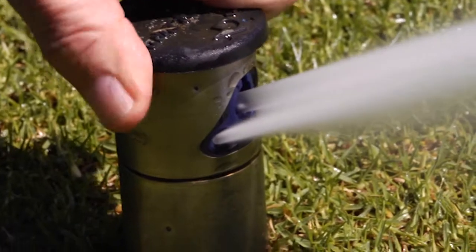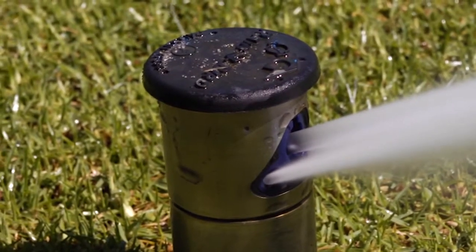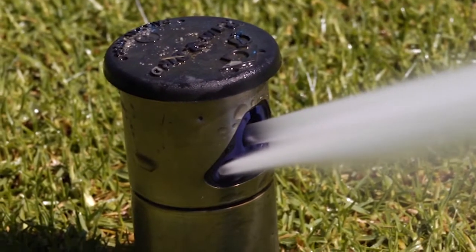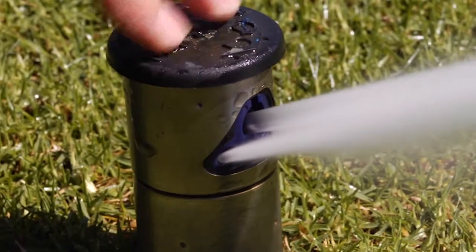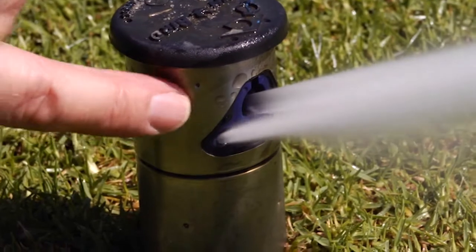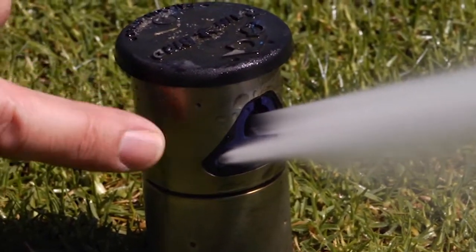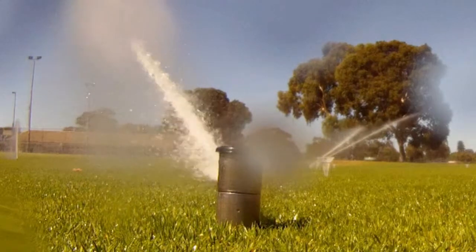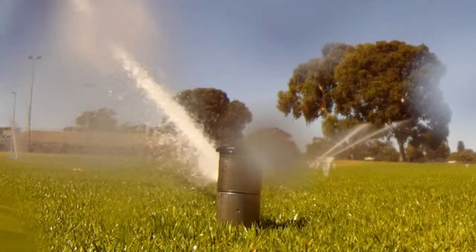This is also a good opportunity to check the nozzle sizes installed in the sprinklers. If the nozzles are color-coded, this is a simple process. But if they are not color-coded, then it's a bit more complicated. In some cases, this can only be done by removing the nozzle, which of course can only be done when the system is turned off.